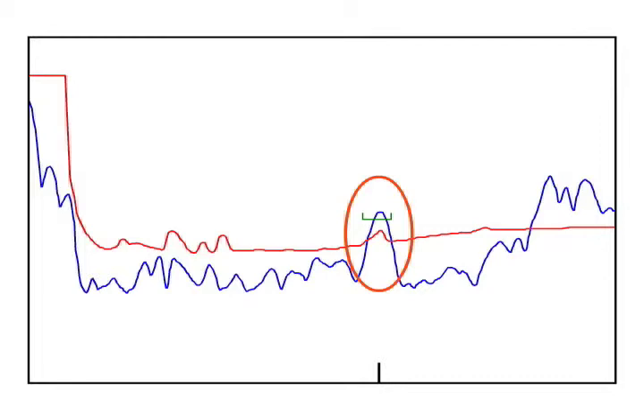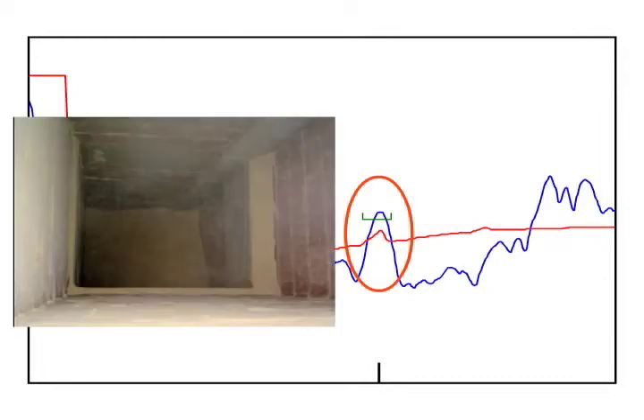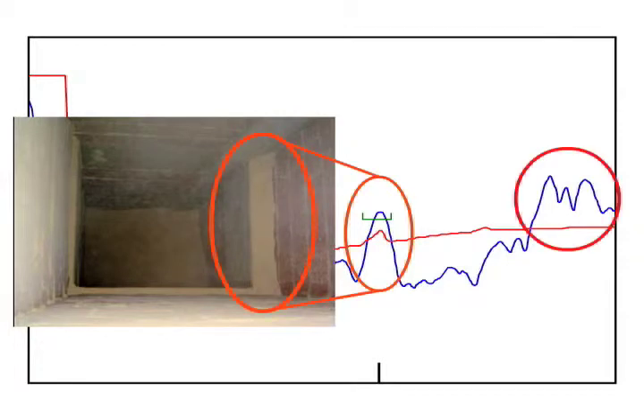Then we did a visual inspection of the silo and manually dipped our level. This is what we saw. That nice echo we saw near the top was caused by a shelf within the silo. Our material echo was somewhere hidden in the mess at the end of the echo profile.